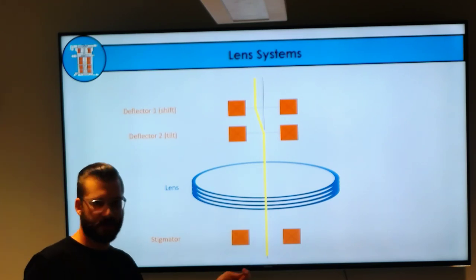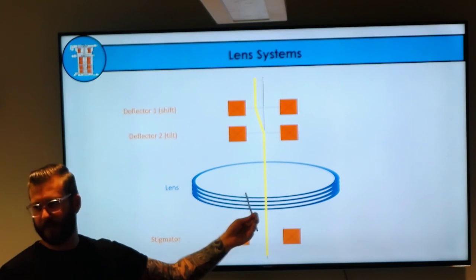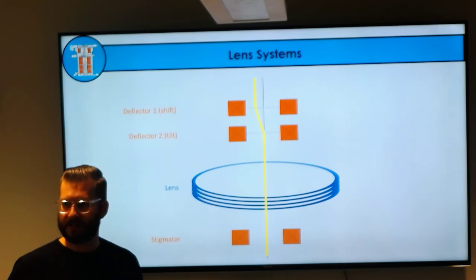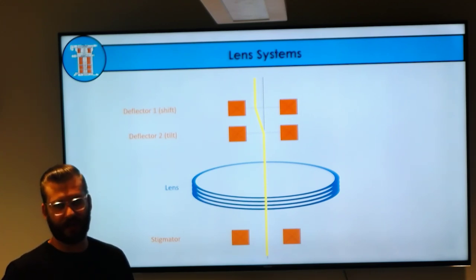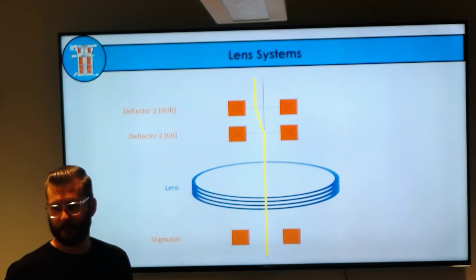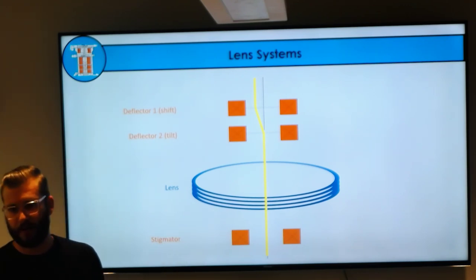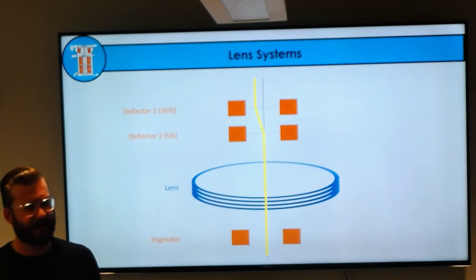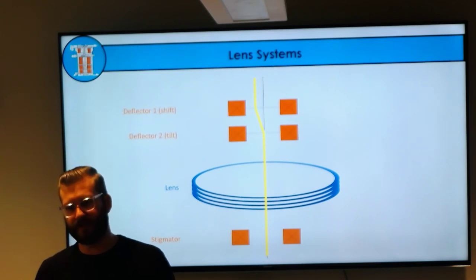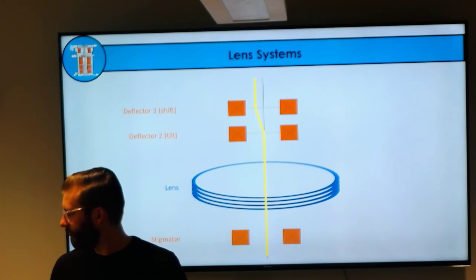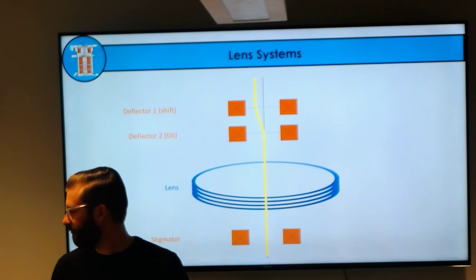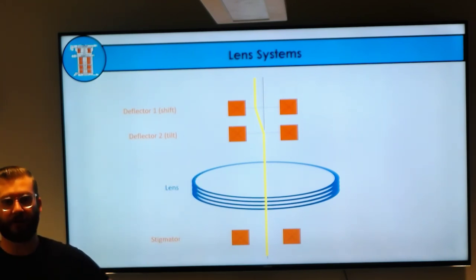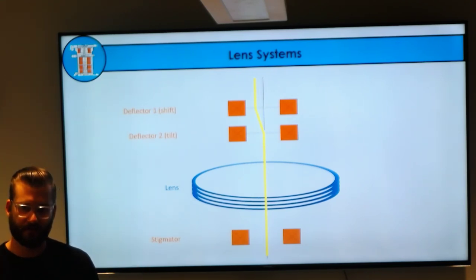The other component of a lens system are stigmators, which come after the lens. The magnetic field generated by these lenses is never perfect—one side may be stronger than another. Sources of these imperfections include contamination, which actually causes charging and astigmatism, and temperature shifts. For our really nice microscopes you don't operate in the same room because just your presence can change the temperature, affecting the water cooling system, changing the resistivity of the lens wires, changing the magnetic field, and its ability to focus correctly.